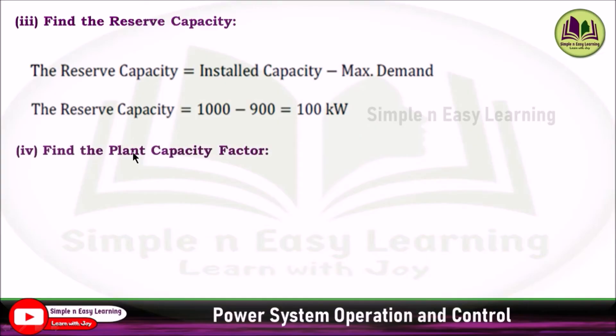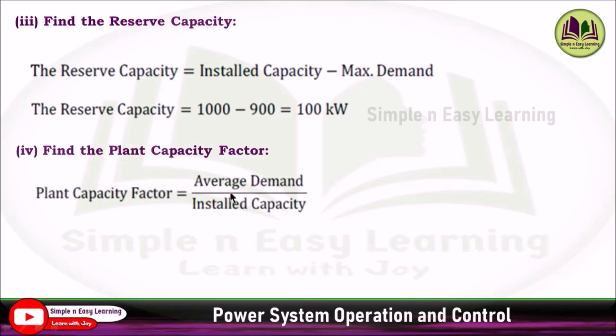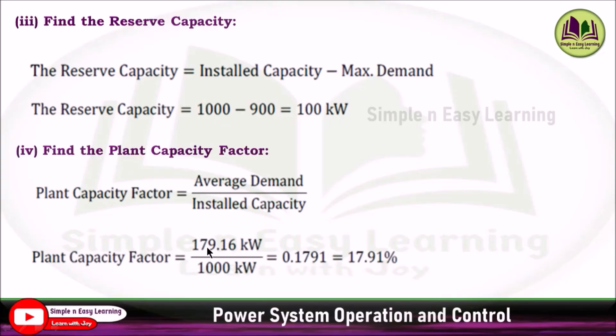Find the plant capacity factor. Plant capacity factor equals average demand divided by installed capacity. Average demand is 179.16 kilowatt divided by installed capacity of 1000 kilowatt, giving a plant capacity factor of 17.91%.